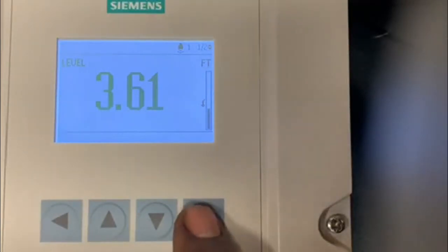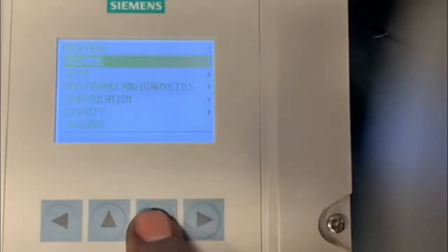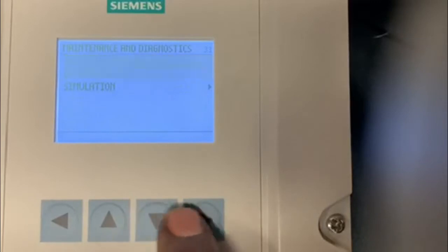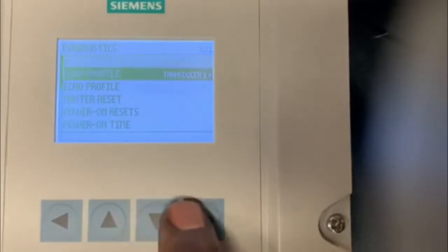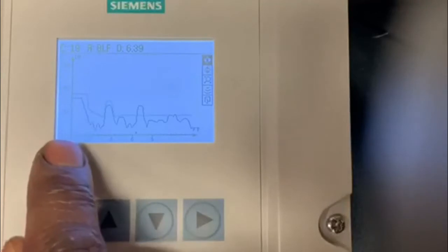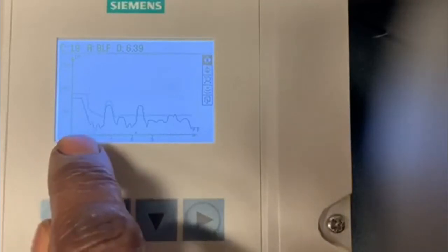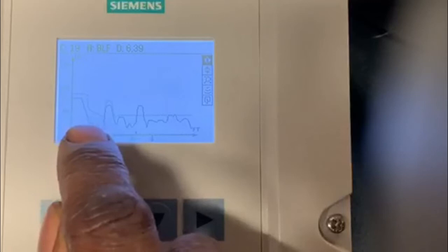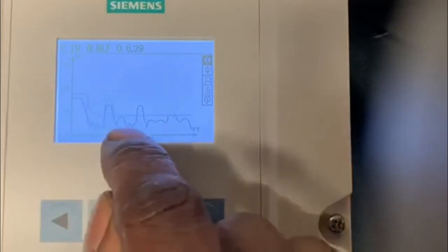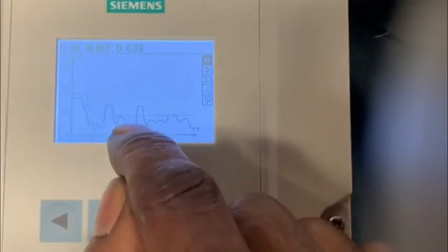If you want, we can actually jump back in and take a quick peek at what that looks like now. And as you can tell, the dotted line, or our TVT curve, superimposed itself around the false echo, leaving only the true echo left.